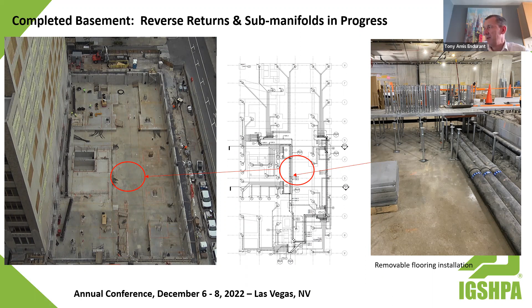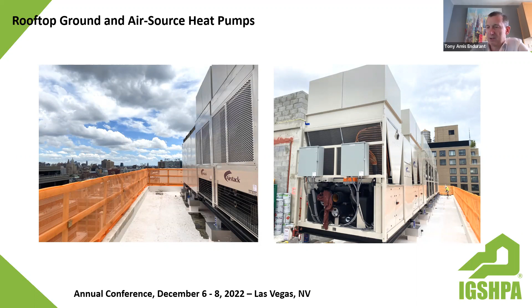Like I said, the heat pumps are now on the roof of this particular building. What I like about the multi-stack units here is that they will operate in ground source heat pump mode or air source heat pump mode, which makes for a great hybrid solution, especially for long-term management and resilience of a solution.